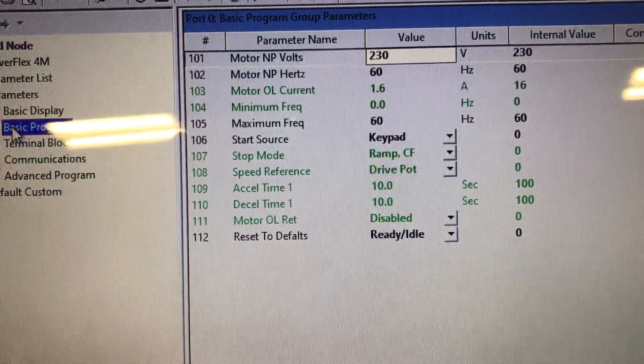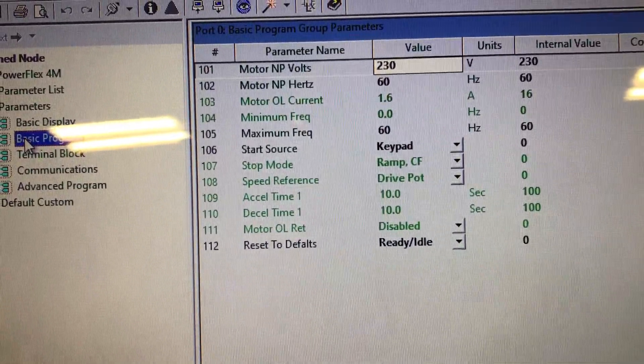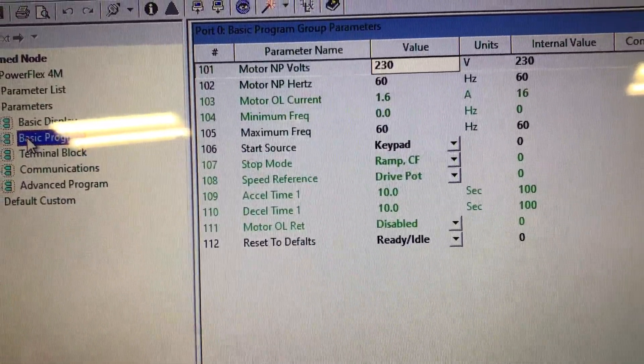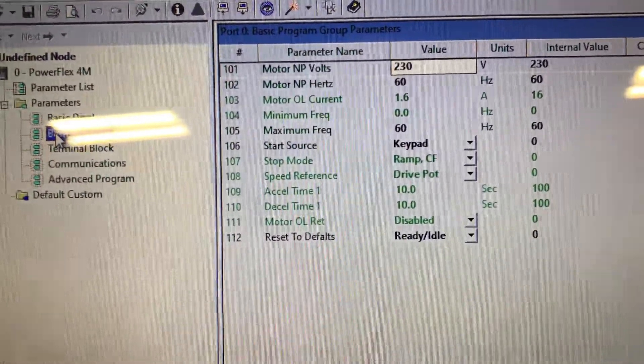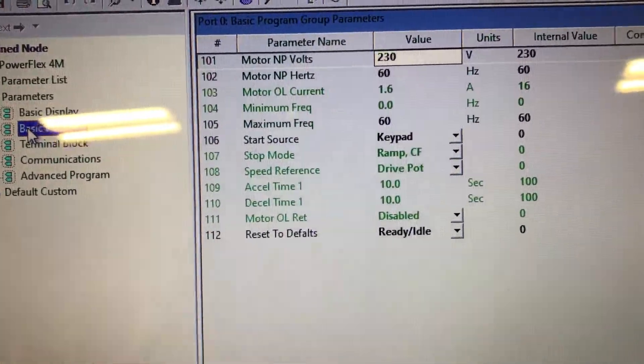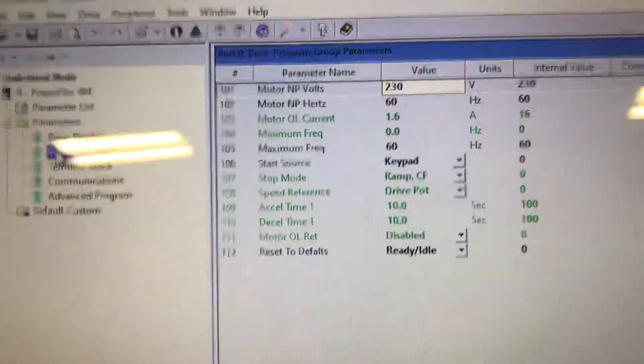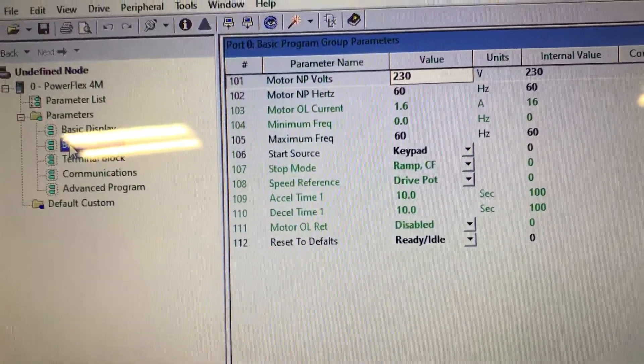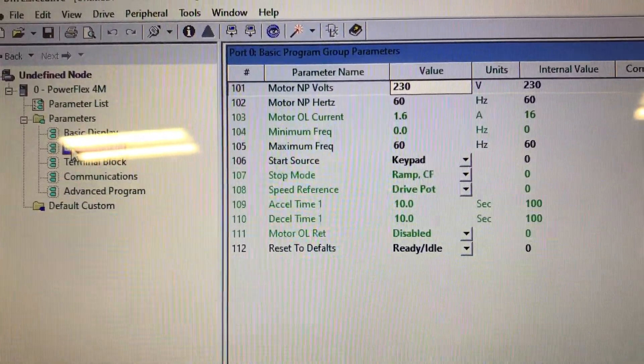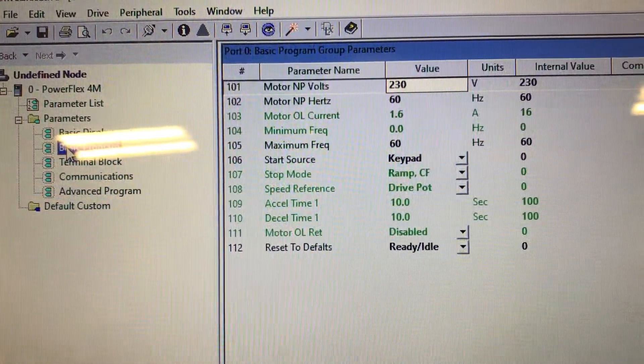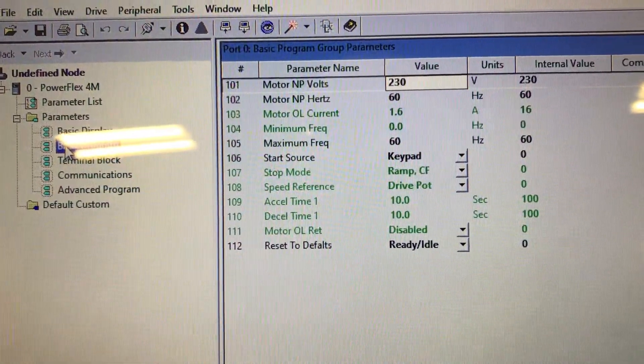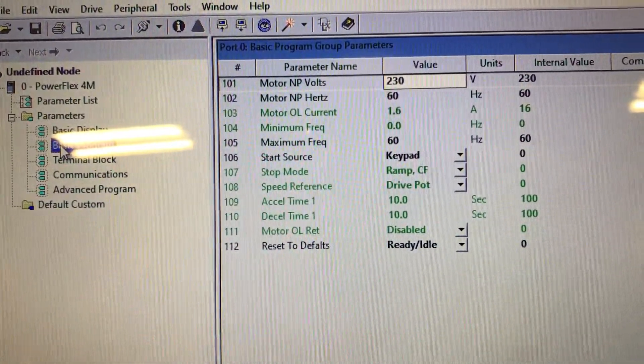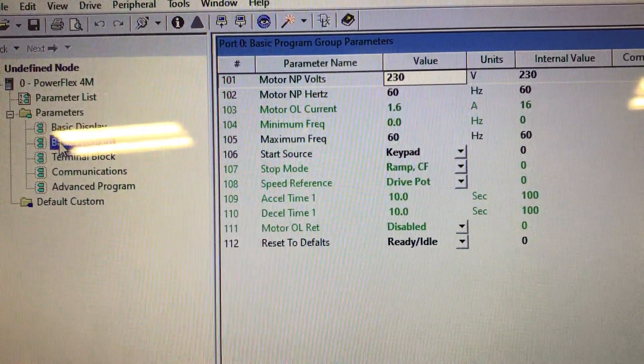Stop mode is ramp, and the multiple differences there is the ramp means that when you push a stop button it will take whatever you put in your ramp to go from that speed to zero.